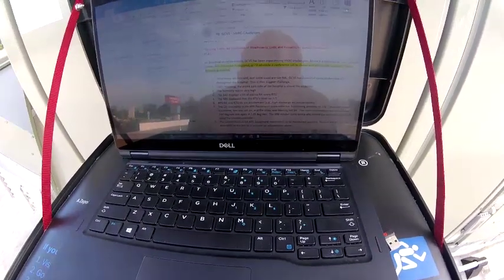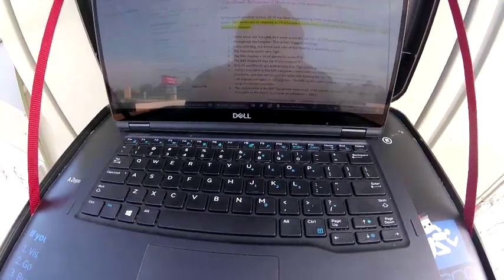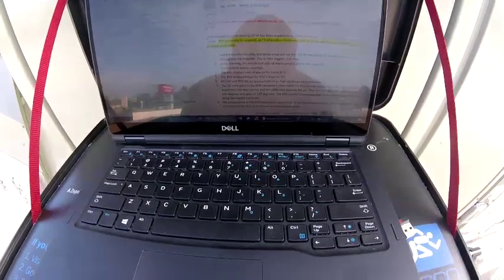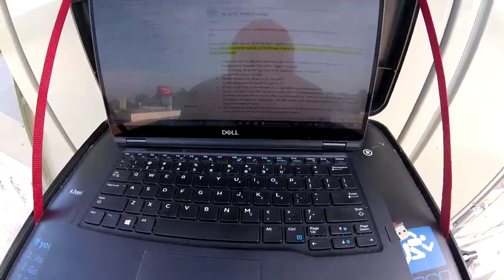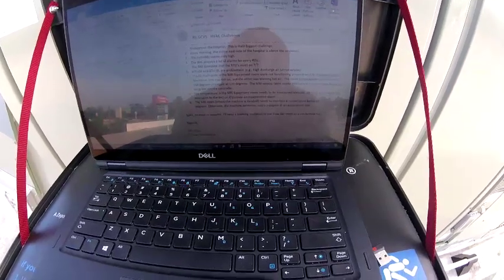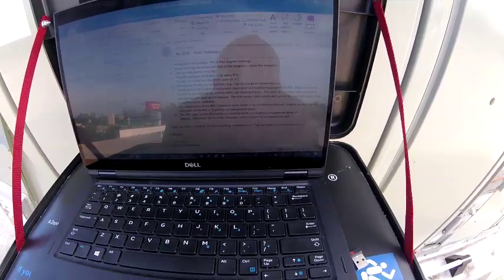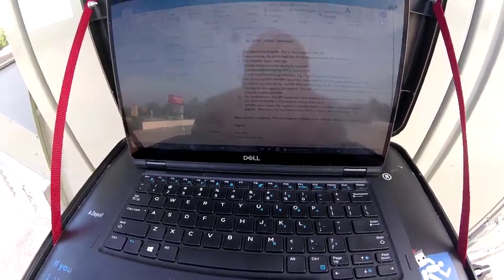Observed around lunchtime, one was not on, the other was not blowing cool air. The room temperature was recorded at 104 degrees and again at 120 degrees. The MRI vendor came out on site and turned the mini splits back on by using the remote control. So I don't know if it was just off or what. The temperature in the MRI equipment room needs to be monitored and alarmed. Options are to, number one, tie the mini splits to the BAS, or two, provide an independent alarm.